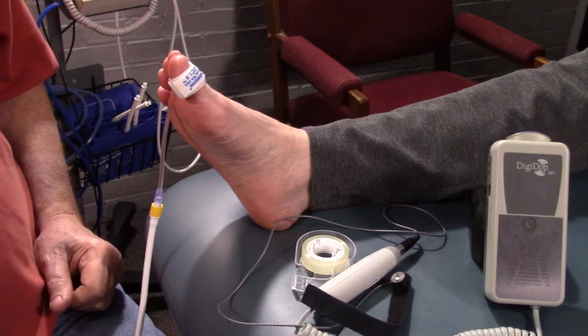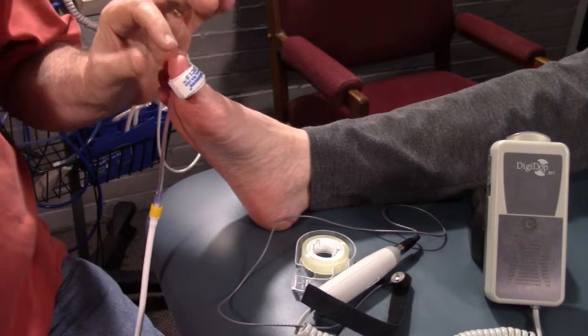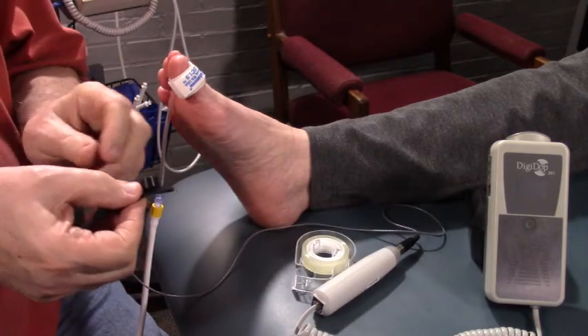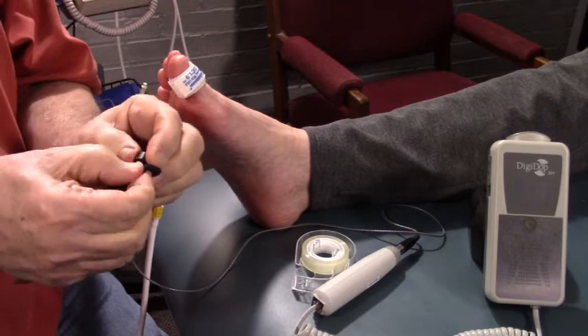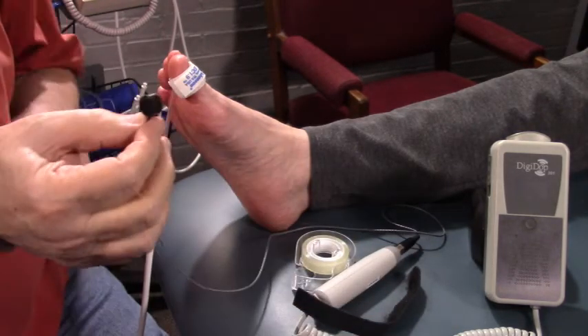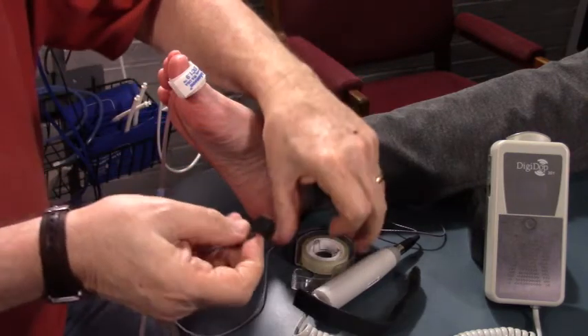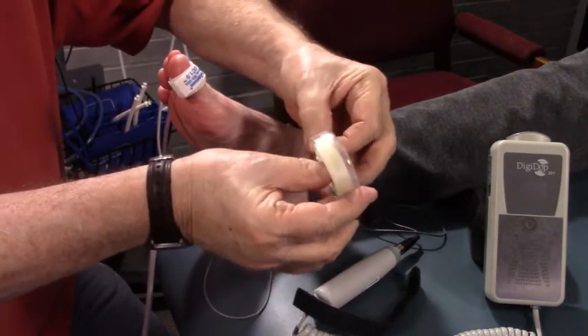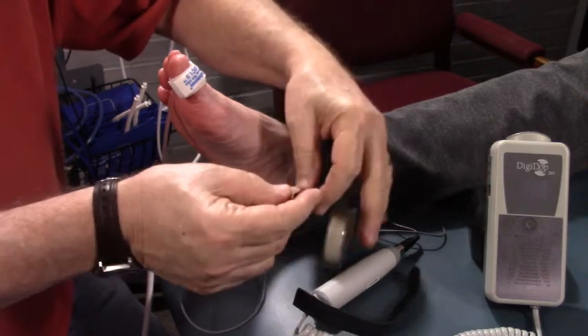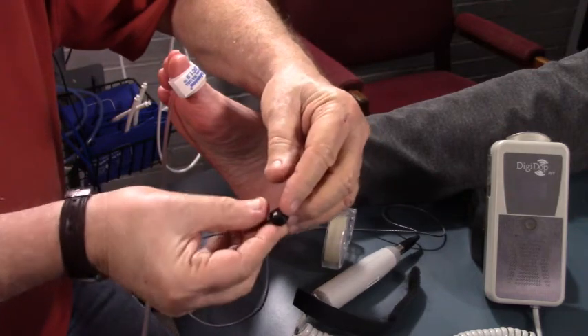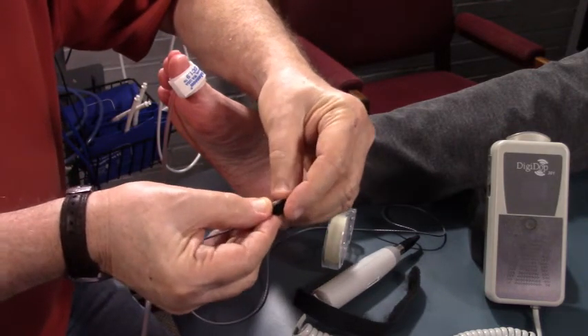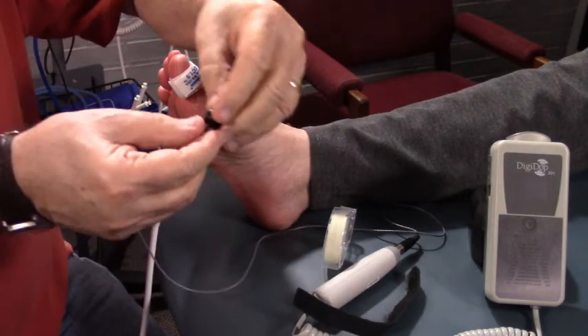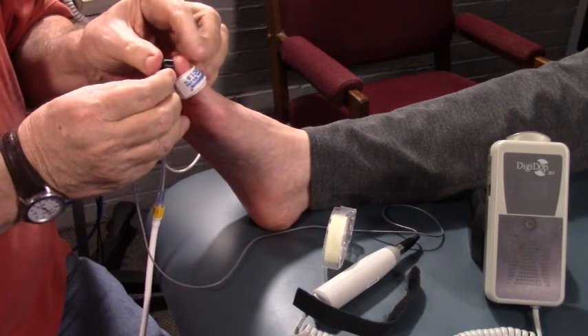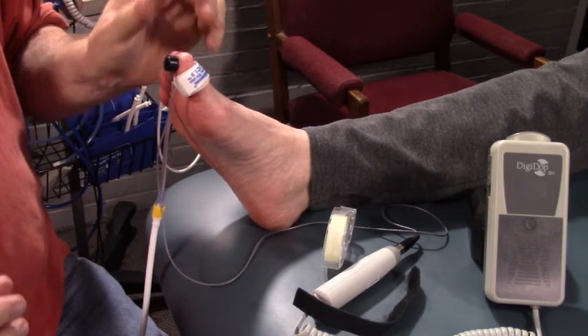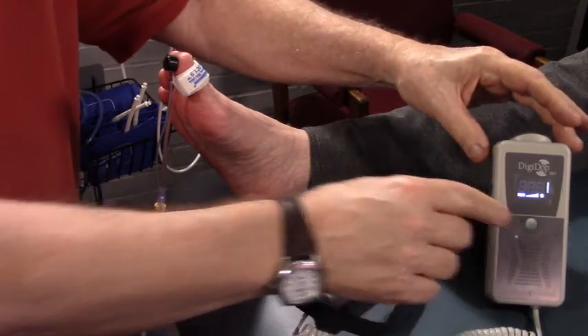Sometimes you will run out of toe real estate on smaller patients and may not have room for the cuff and Velcro strap that secures the sensor without overlapping the cuff. If this happens, simply disconnect the Velcro strap as shown from the PPG sensor. Take a small piece of double-sided tape and attach it to the sensor side of the PPG probe. Hold the taped sensor on the toe for a few seconds to ensure adherence and proceed as before, taking the toe pressure reading. There are many users who prefer this application over the Velcro strap method.